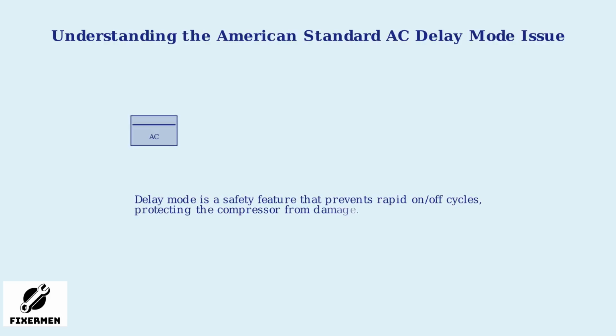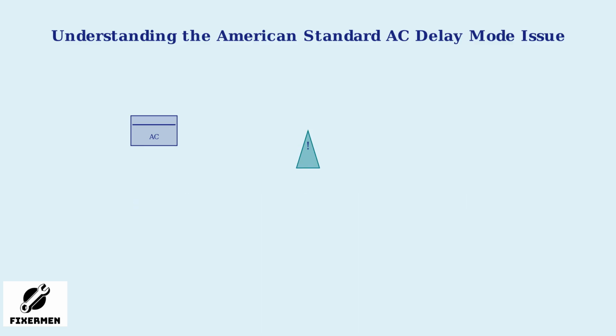Is your American Standard AC stuck in delay mode? This video will help you understand why. Delay mode is a built-in safety feature, usually lasting 3 to 5 minutes, preventing rapid on-off cycles that can damage the compressor. The delay typically lasts 3 to 5 minutes after the compressor turns off, giving it time to stabilize before starting again. When it gets stuck, your AC won't cool properly, leading to discomfort and higher energy bills.